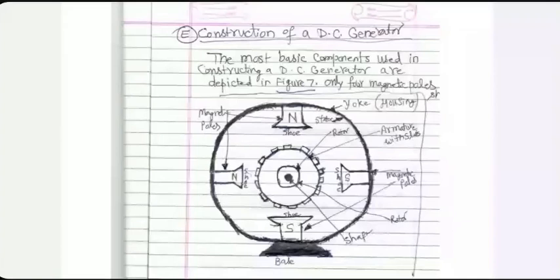The core of the rotor is made of magnetic material because this helps in improving the performance. Iron losses and eddy current losses will be there for sure. To reduce eddy current loss, we use laminations as we did in transformers. Also, because of the rotation, friction loss will be there, windage loss will be there, and on top of it, there will be copper loss in field windings and copper loss in armature windings.